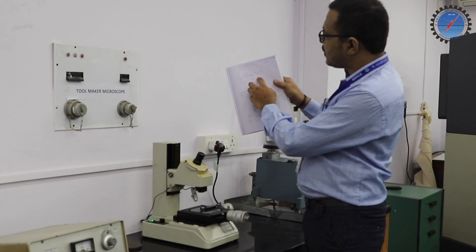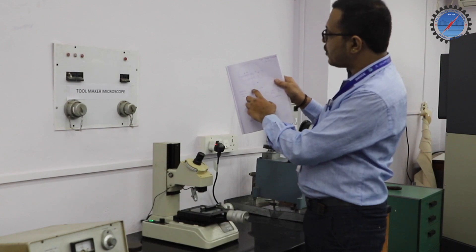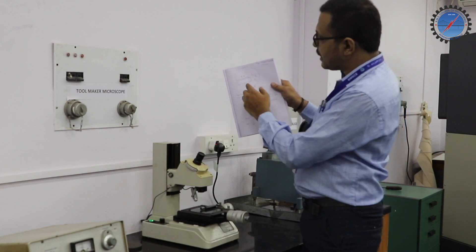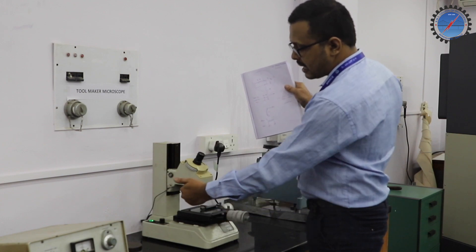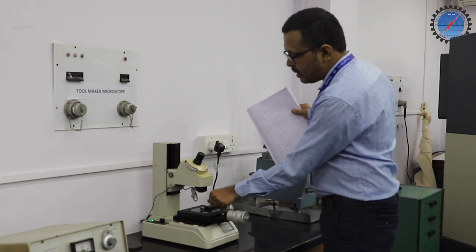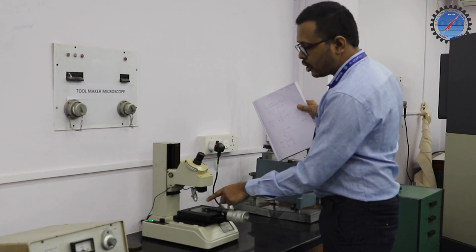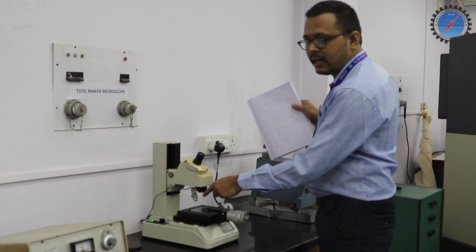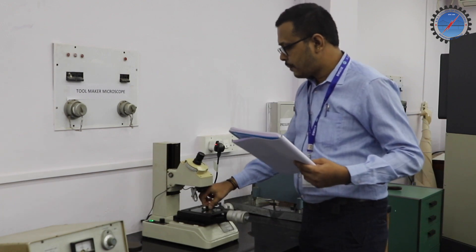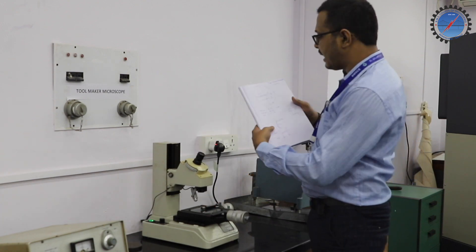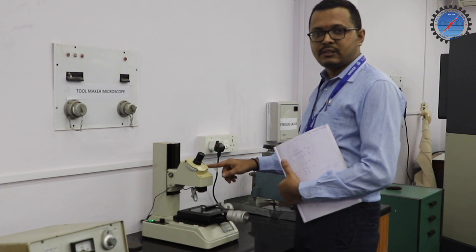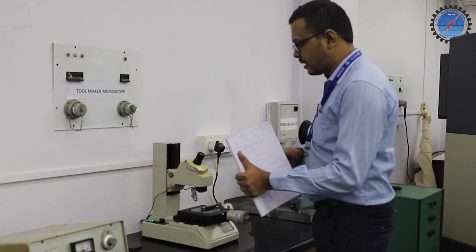Minor diameter is R2 minus R3. The reason we use subtraction is that we do not know in advance which reading is larger. Pitch can be measured using a different scale orientation — place the component differently for pitch. Major diameter, minor diameter, and pitch can be read using the linear scale. Another scale is given for the angle of the system, which we will discuss further.